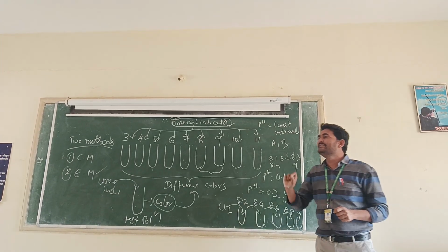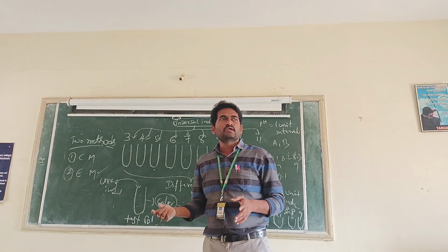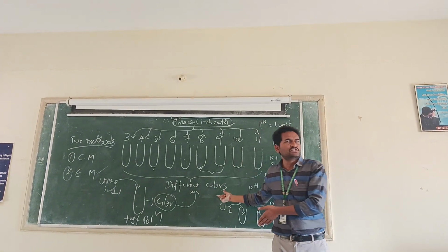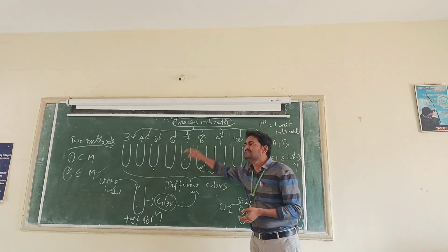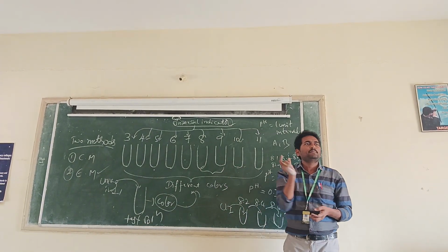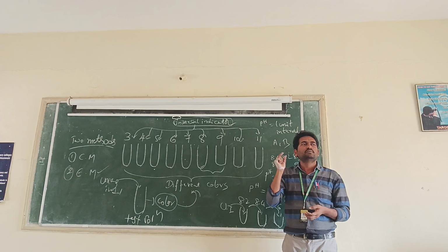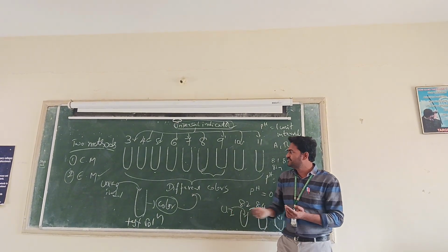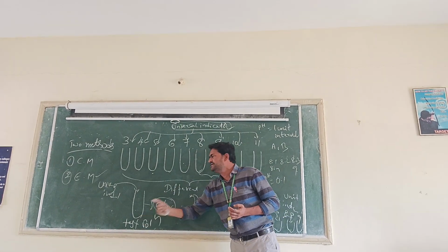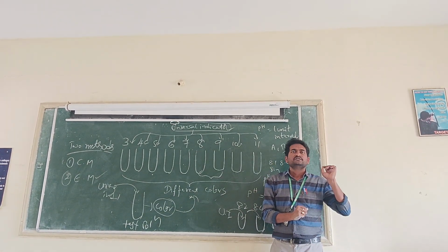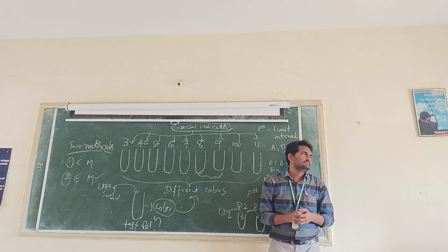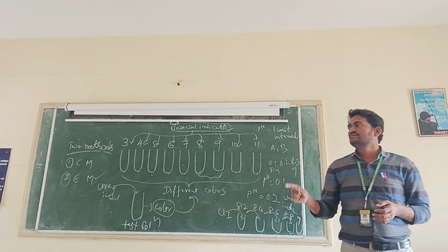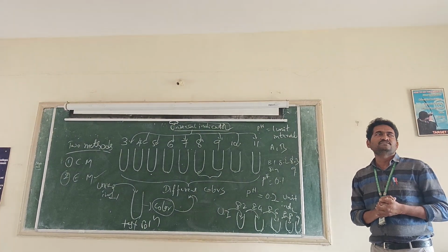Now the glass electrode should be rinsed with purified water, because we immersed it in a known standard buffer solution, and some of that buffer will stick to the glass electrode before we dip it in the test solution. So we rinse it properly with purified water. After rinsing, we dip the same electrode in the test solution. Now it will show the reading on the readout device, and that pH is considered the pH of the given test solution.